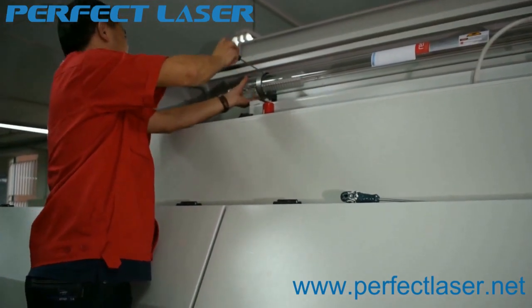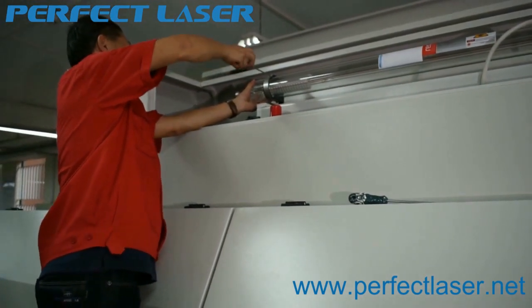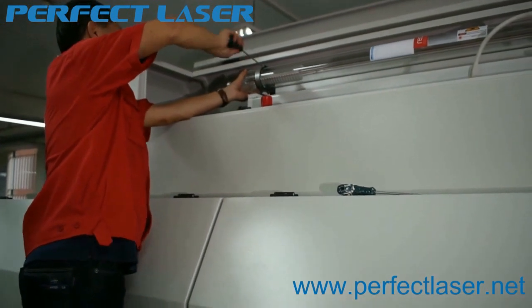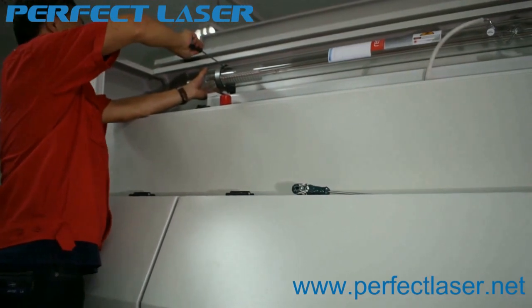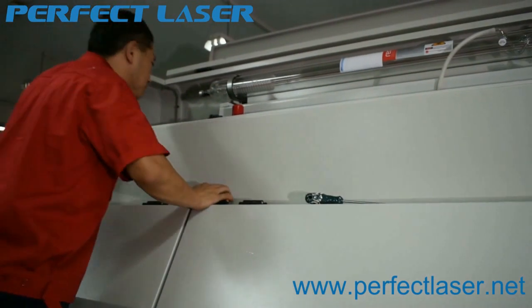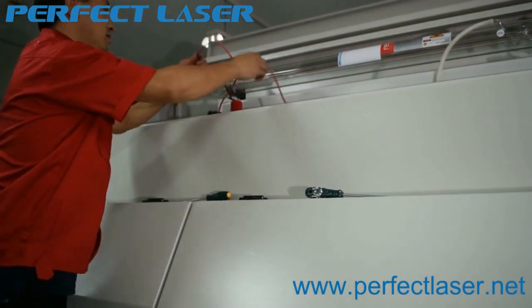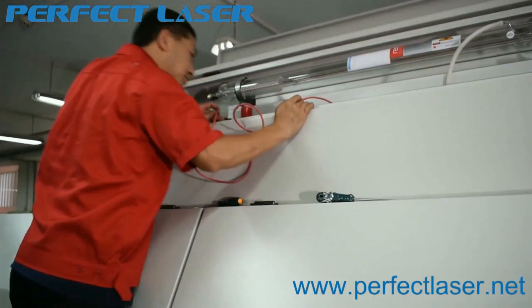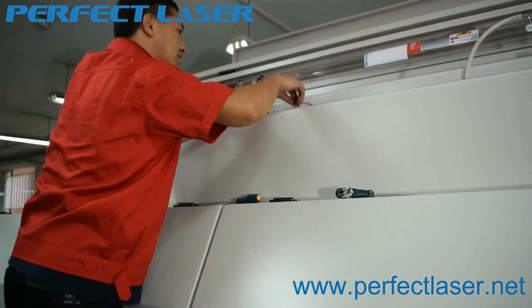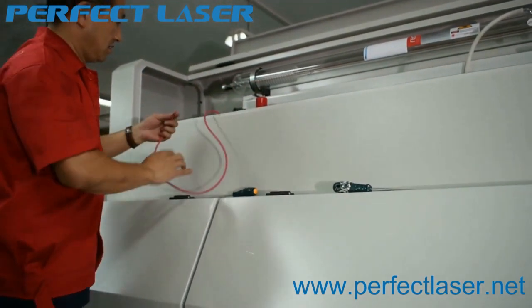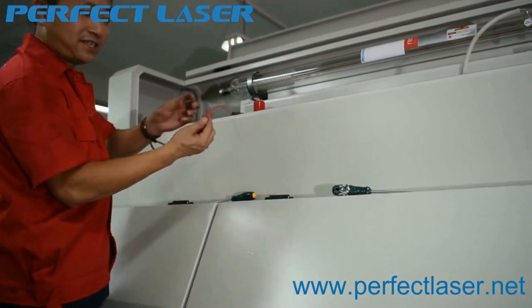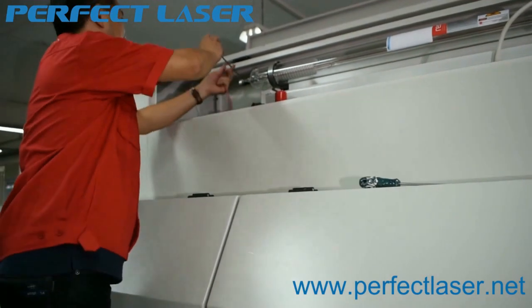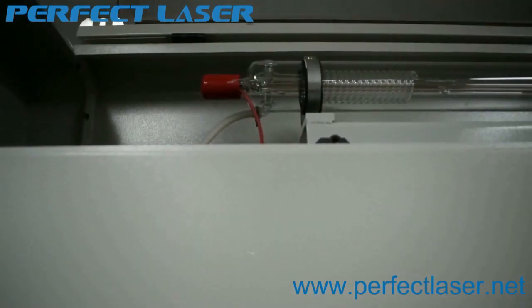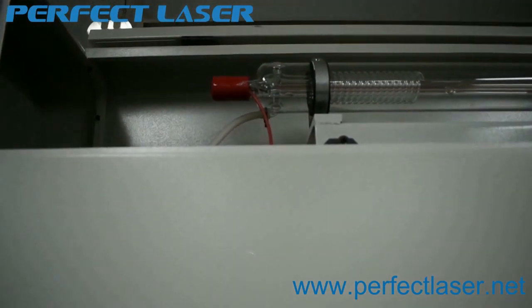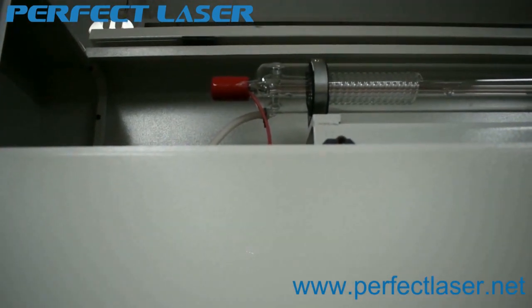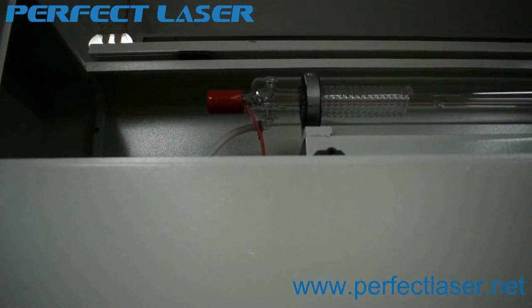Firstly, lock the screw. Make sure the laser tube cannot be moved. And also find the red color cable. This cable is the high voltage cable. Connect it to the left side of the laser tube. This is the high voltage cable. Make sure to connect the wire cable into the left side of the laser tube and then use the red cover to cover it.